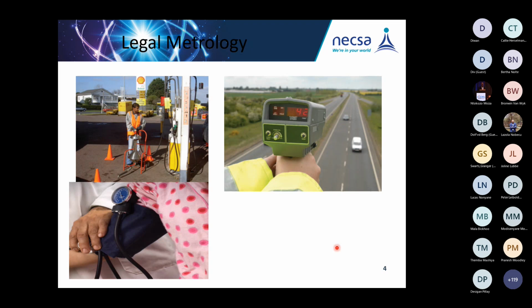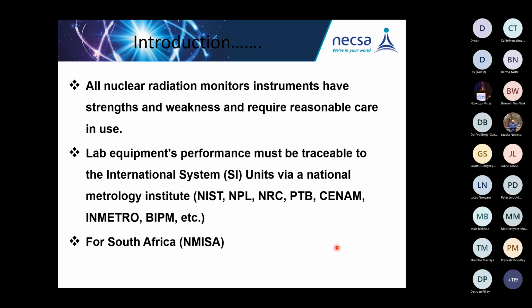When we go to the hospitals, most of the devices were not actually calibrated, but these days we can see that things are changing, and we do appreciate that, because most of those instruments carry a huge decision. Unlike when you go to check your BP, the equipment can give unrealistic results, and the doctor might place you on chronic medication, whereas it was an instrument which was not calibrated. So with calibration, we always check the verification. It's a process where we check: is this instrument still fit for the purpose for what it was intended for?